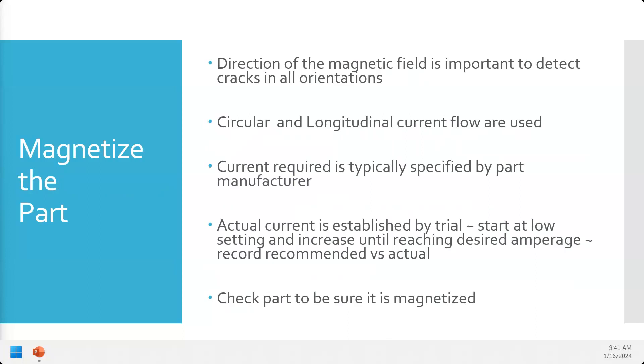Our machine has a dial that looks like a volume control knob — numbered 1 through 10 — rather than a dial marked in amps. The reason is that current depends on voltage and resistance: different size and material parts placed in the machine have different resistances. So the same dial setting of, say, five will produce different currents with different parts. You may have to adjust the dial until you reach the required current for that specific part.